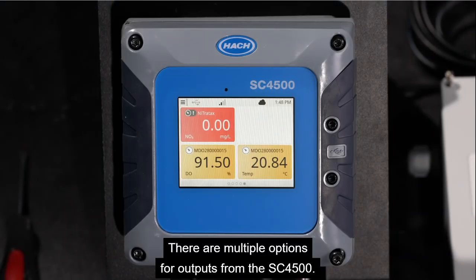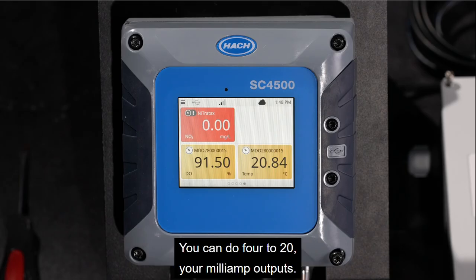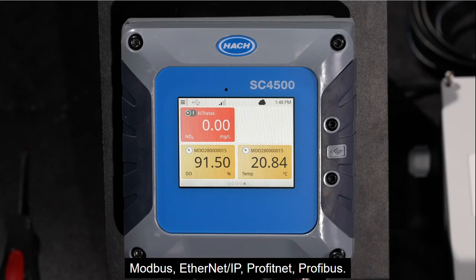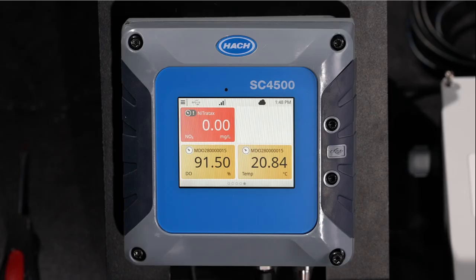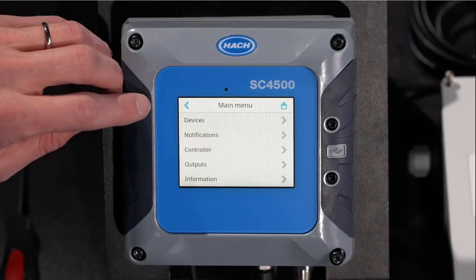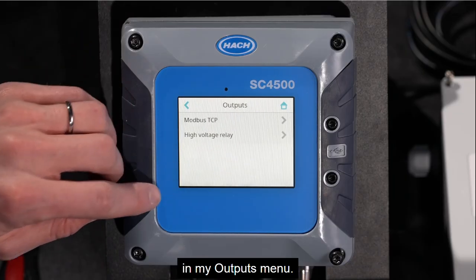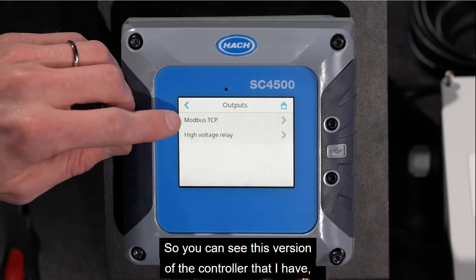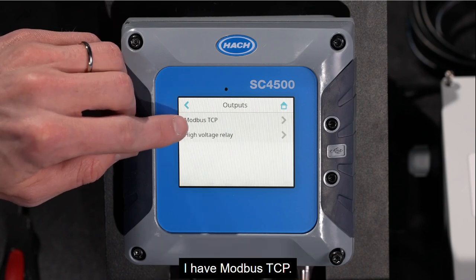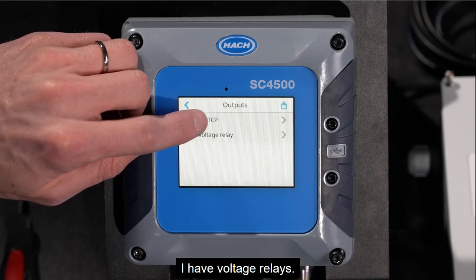There are multiple options for outputs from the SC4500. You can do 4 to 20 milliamp outputs, Modbus, Ethernet IP, Profinet, Profibus. These are all managed in my outputs menu. In this version of the controller, I have Modbus TCP and voltage relays.